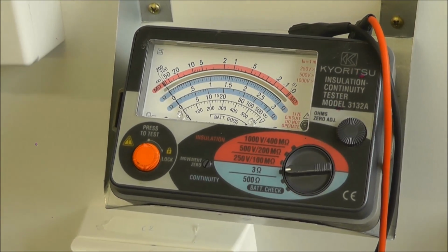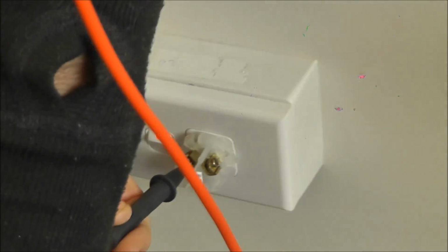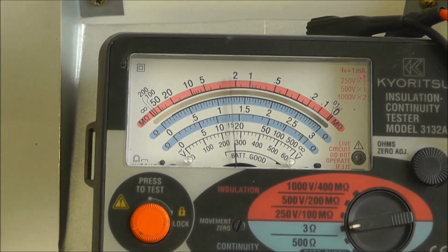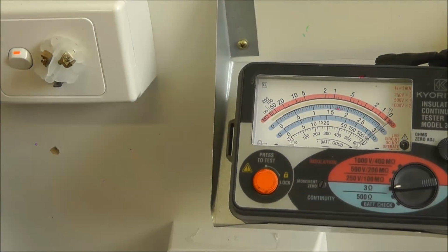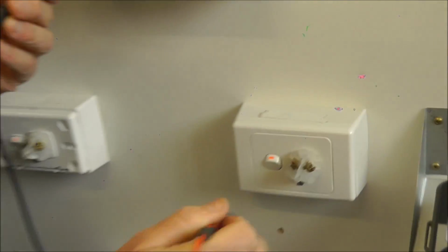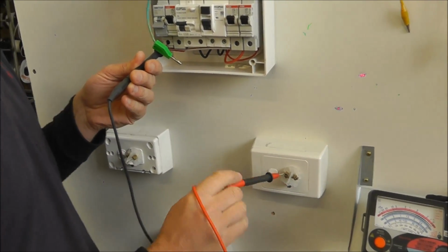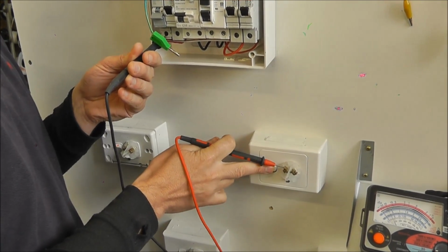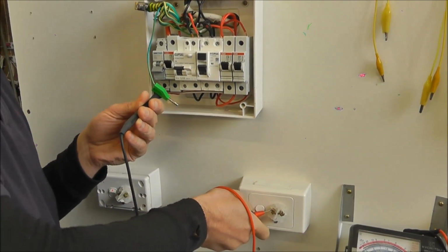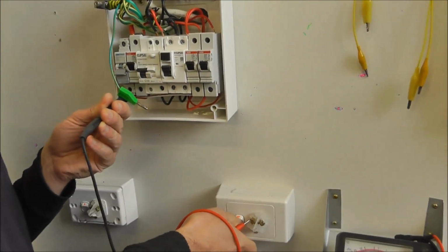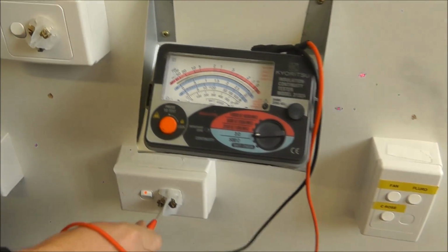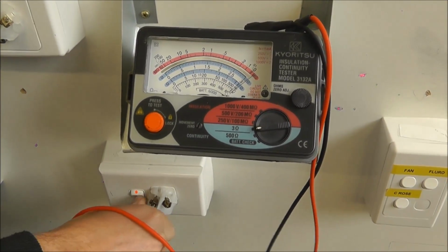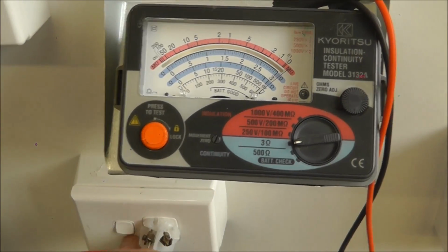Socket outlet 1 active is switched. I'll just go through them all. Socket outlet 2 is the active switch, yes. Socket outlet 3. Oh, now I just want to show people what happened then, between here and here. Oh, no, it didn't go. Well, the RCD went before, but anyway, that active switch there, that's good news. Things looking sharp so far. Over here, whoa, the active is not switched. Bad.